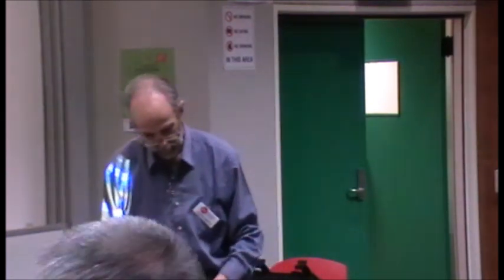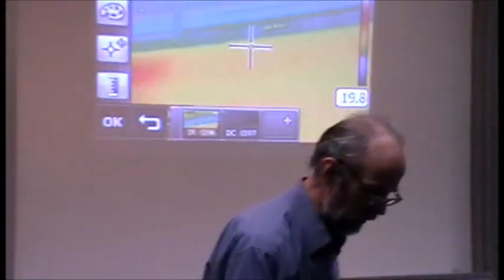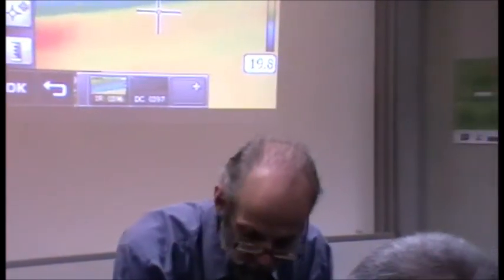Can you check? I was reading if you put a piece of crumpled alfoil and measure the reflectivity from that, can you then use that as an approximate for your emissivity? Not for emissivity. No, it's got to equal one. What that crumpled aluminium does is it helps you find what the reflected temperature is that you should put in the camera for the reflected temperature. Not the emissivity number, but that reflected number. Yeah. And that's quite different.